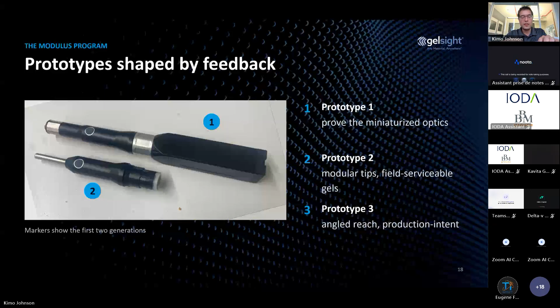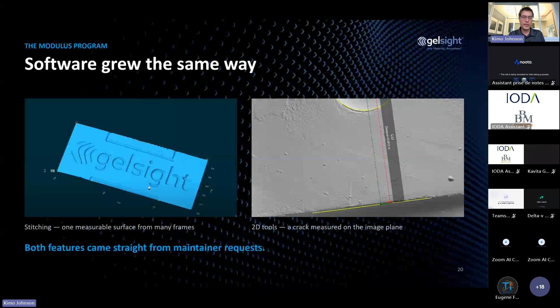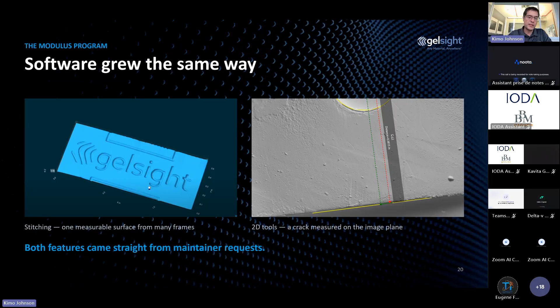And software feedback: we received a lot of feedback along the way around how you can measure larger areas. With this, in our single probe, we developed stitching algorithms where you can take multiple scans and blend them together and do a single measurement. And also, not just 3D measurements like depth, but being able to measure two-dimensional distances, like the distance between an edge and the center of a hole, or diameters. There's a lot of rich two-dimensional information in all of our scans. So we developed software features based on requests from people using the devices in the field.